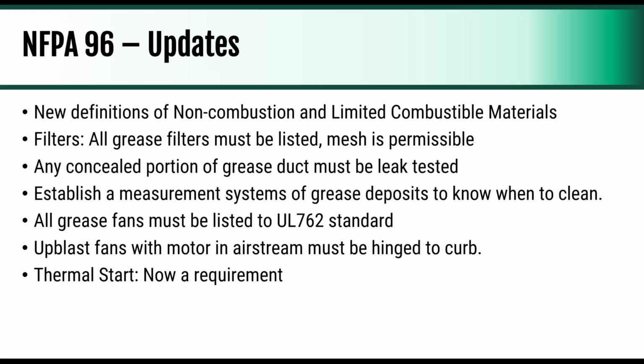Upblast fans with the motor in the airstream. So just think about the mushroom type fans on the top of, call it 80 to 90% of restaurants. They need to be hinged to the curb. Again, most manufacturers were doing this because it's an access point for cleaning the duct. And the last bigger one, it's not a huge change, but thermal start is now a requirement.